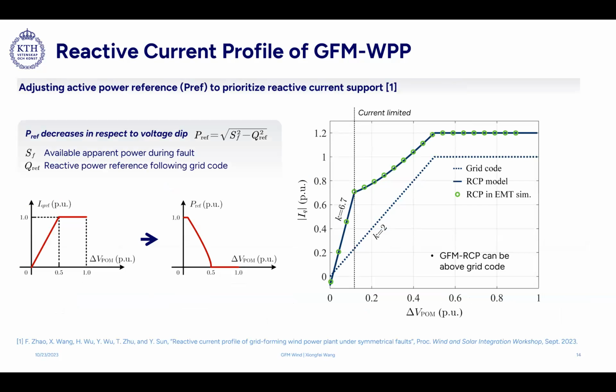Then we can translate this reactive current requirement to the active power reference adjustment with a nonlinear function. Then we try to adjust the active power reference for the wind turbine whenever they reach the current limit. Then we can check if the output current can meet the requirement of the present grid code. Here we just show you the three curves.